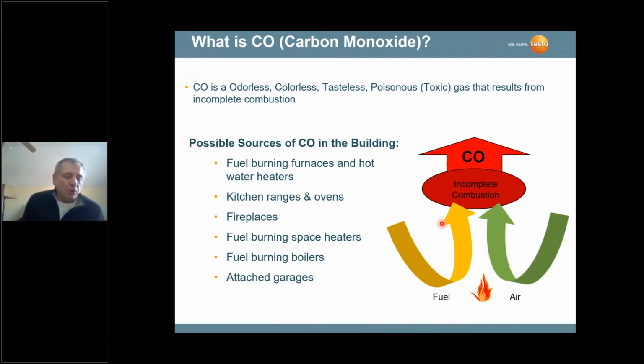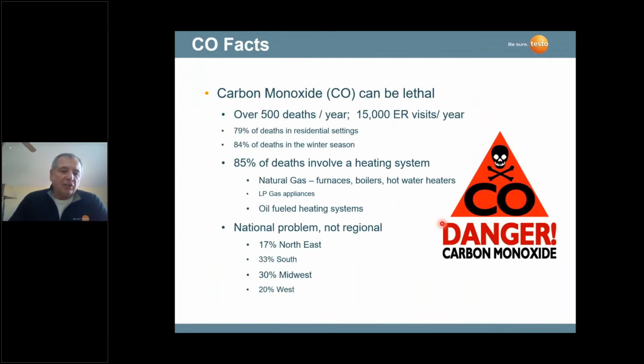Our burners, our boilers, our furnaces are designed very safe. They are designed to minimize the carbon monoxide, to make sure that the flue gases are going out the stack at the right velocity, so that we don't have any issues with people that are in the building. So the furnaces and the boilers are designed safe. It's our job to maintain the safety of these furnaces and boilers by checking carbon monoxide. That's one of the critical measurements for combustion safety.